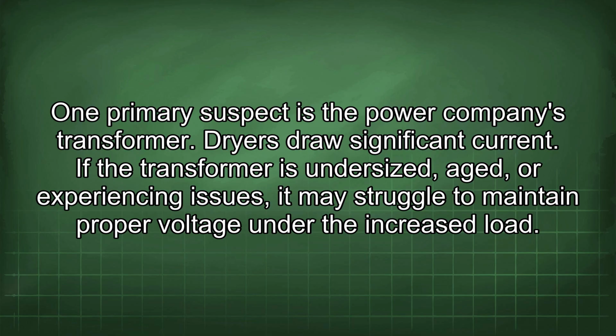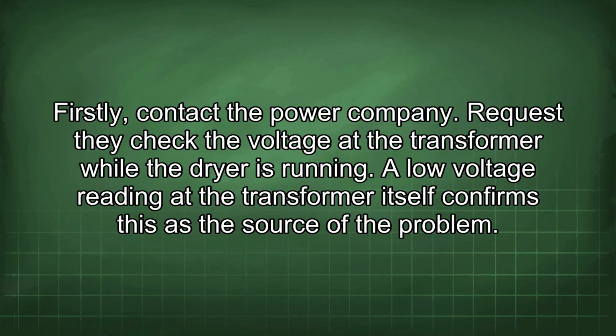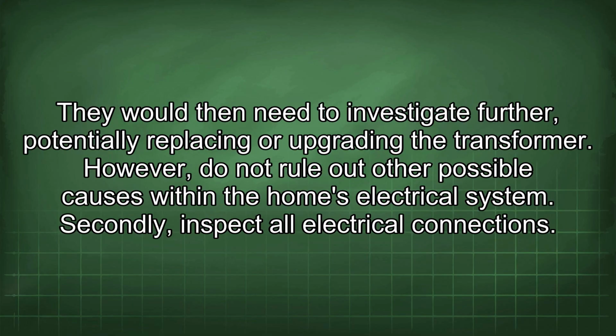Dryers draw significant current. If the transformer is undersized, aged, or experiencing issues, it may struggle to maintain proper voltage under the increased load. Firstly, contact the power company. Request they check the voltage at the transformer while the dryer is running. A low voltage reading at the transformer itself confirms this is the source of the problem. They would then need to investigate further, potentially replacing or upgrading the transformer.